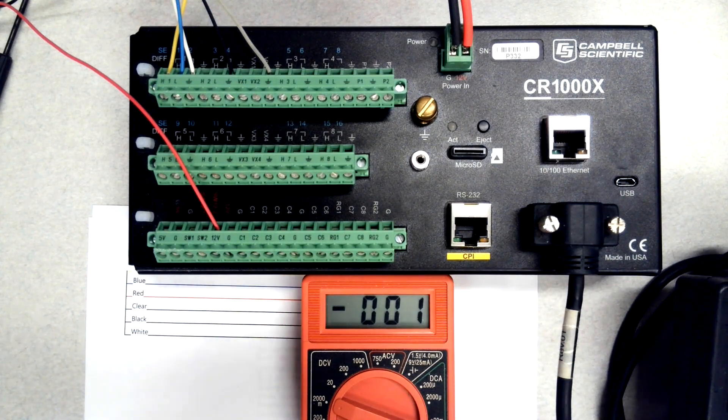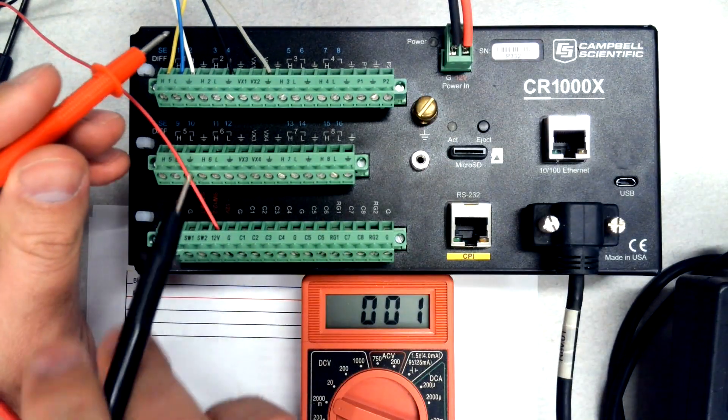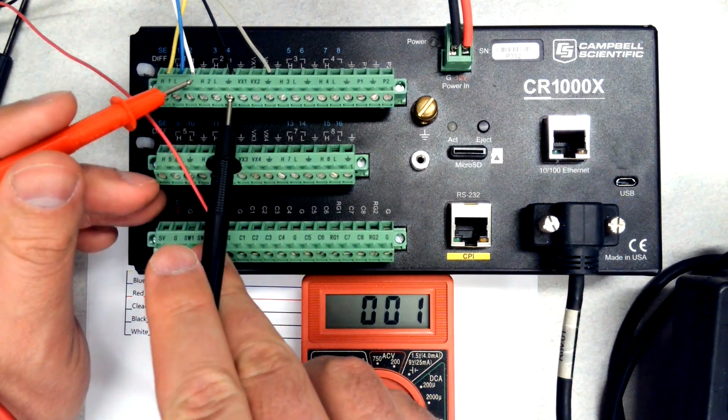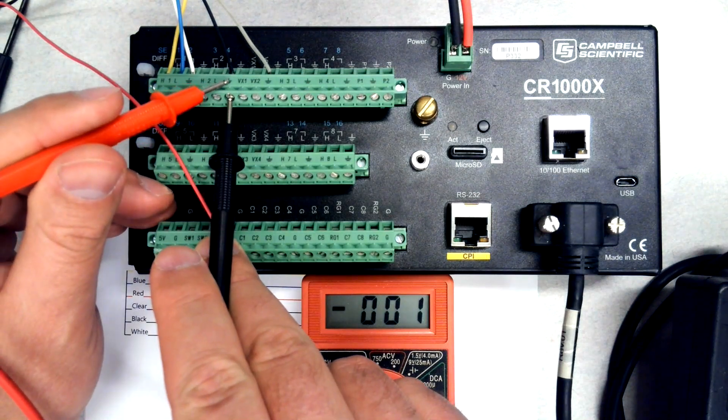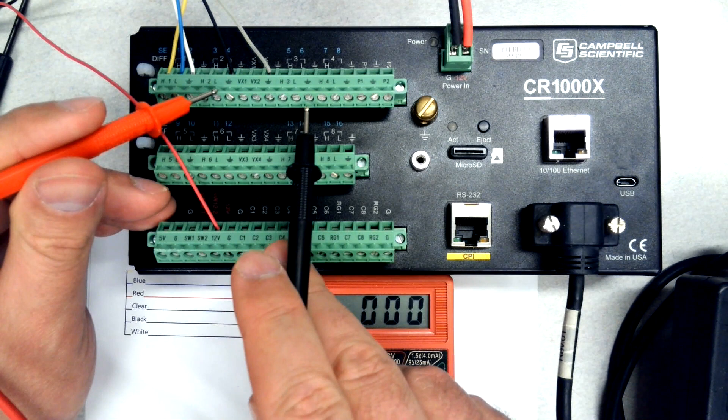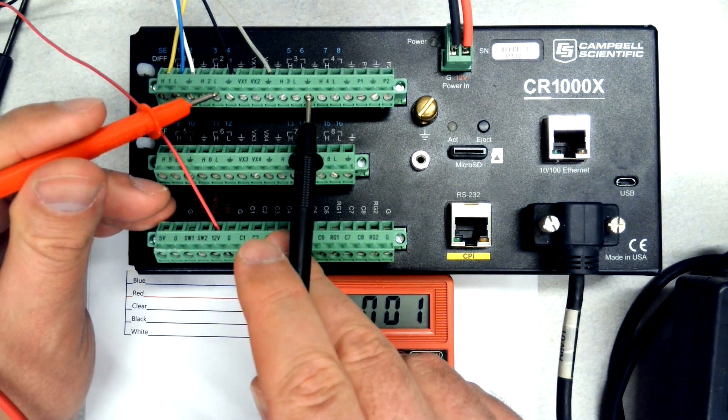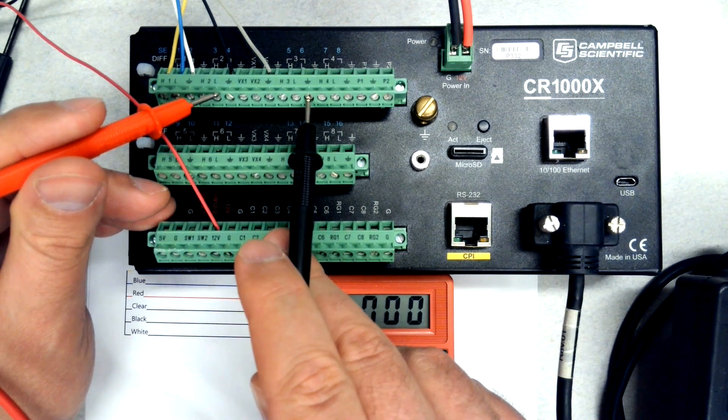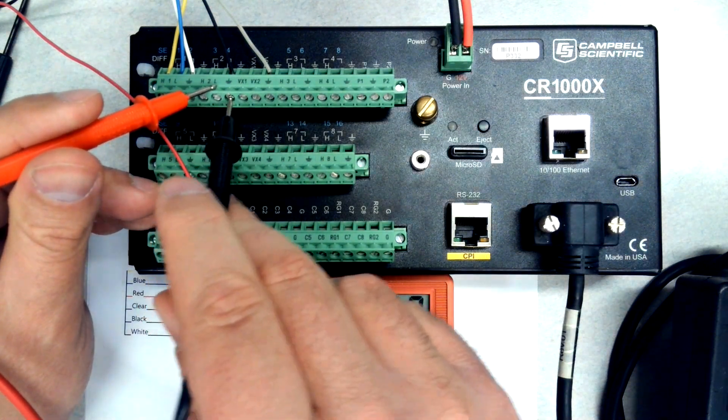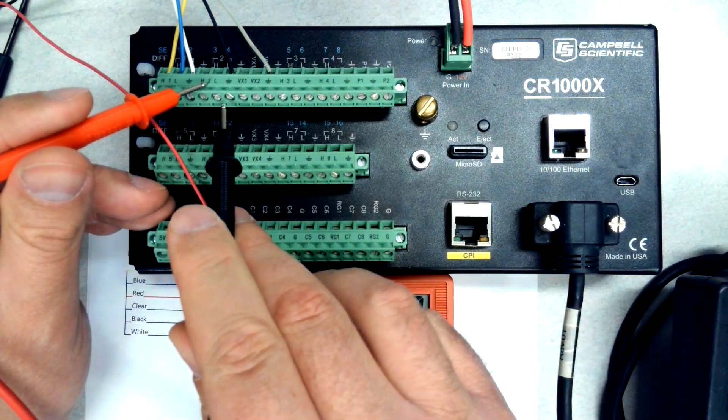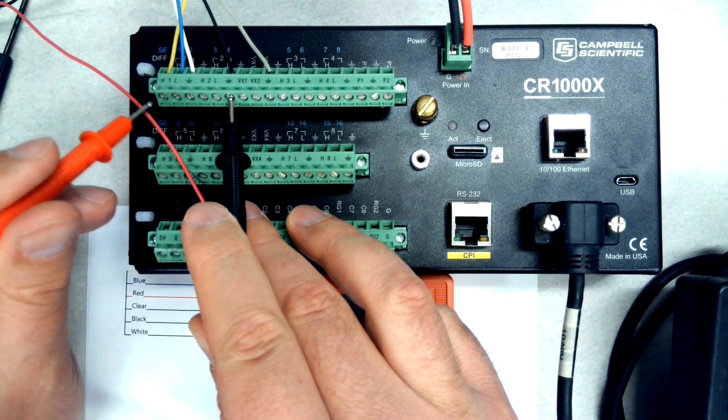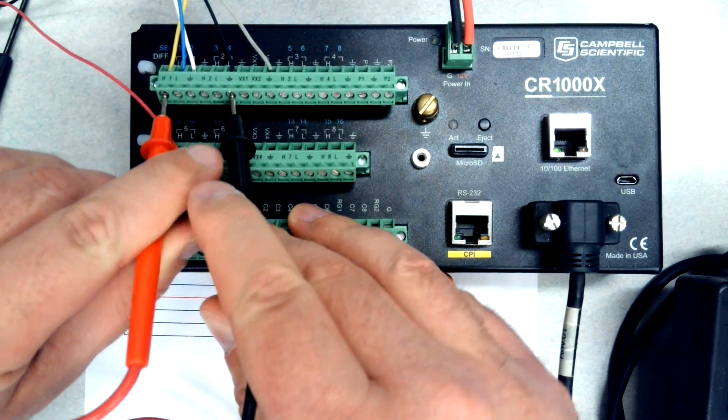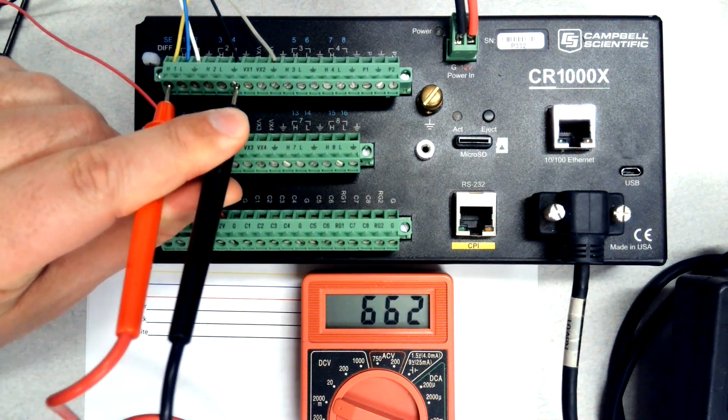Arrange it where you can see your display easily. Put your reference probe on one of your grounds. These screw terminals, if they're closed, you can get good electrical contact. If I was to put this on an open terminal, the loose screw can not be a very good electrical contact. So you want to put it on one that's closed or you can hold it against the ground lug. I'm going to use this ground terminal and I will check the yellow, which will be my temperature signal.